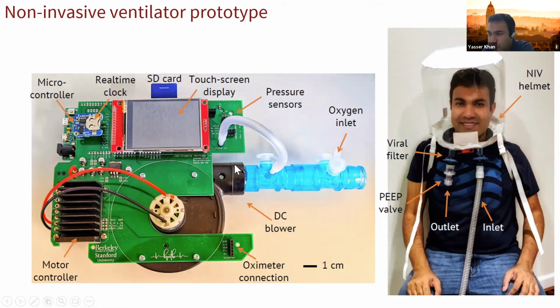The way the system works is we have a blower. So this DC blower compresses air, and we have a motor controller that controls the blower. And then to control the unit, we have a microcontroller and also a touchscreen display. And we have a way to log the data in an SD card. We also have a real-time clock, and it has a bunch of sensors for pressure, flow, and also we have an oximeter connection. And on the patient side, we have this helmet.